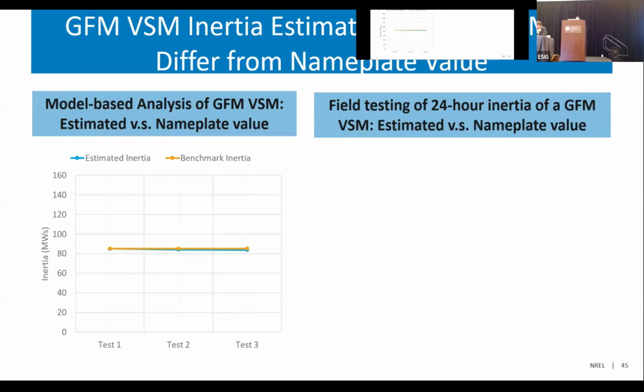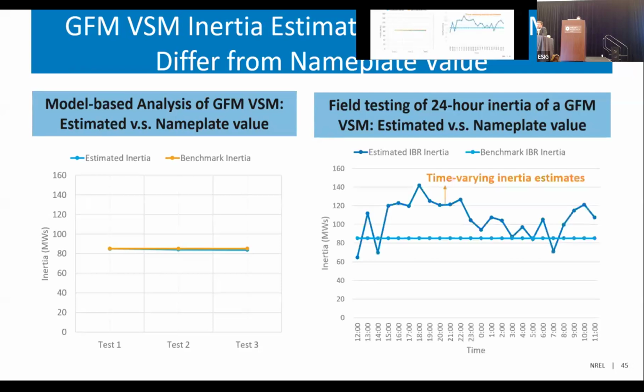This time the measured or estimated inertia perfectly aligns with the nameplate of the VSM, which is 80 megawatt seconds. However, when we deployed that to our field data, the results were still better and much closer to the nameplate, but we still see this time-varying inertia estimation result. We later found out this is because of the modeling gap between our generic VSM model and the real control that has been implemented into this VSM. So the main takeaway is that for future inertia quantification of inverter-based resources, field testing and an accurate vendor model are really essential when doing the evaluations.